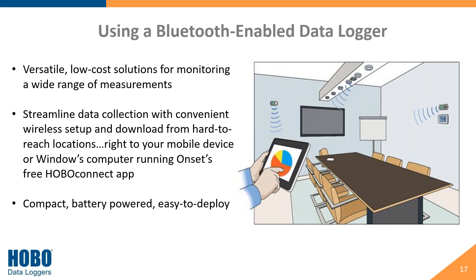I see our Bluetooth loggers frequently used for energy audits or HVAC monitoring at a client facility or school, where you need to collect data periodically — say once a week — without interrupting a classroom or office. The Bluetooth signal has about 100 feet line-of-sight range. If loggers are tucked up near an HVAC unit, nine times out of ten you can stand right outside the classroom door, open the HOBO Connect app, connect to the logger, offload the data, restart it, and move on to the next one without ever accessing the room.